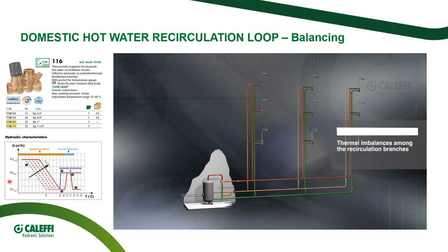kV disinfection is the hydraulic characteristic when the valve is in the disinfection phase, and that is the value that you have to take into account when evaluating the thermal disinfection flow rate. It's not the maximum, it's not the minimum, there is a specific one that is reported in the technical documentation and differs from the kV value in normal operations. So when sizing, we take into account both of the values.